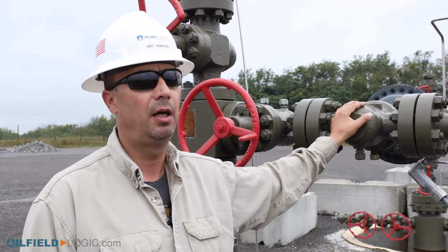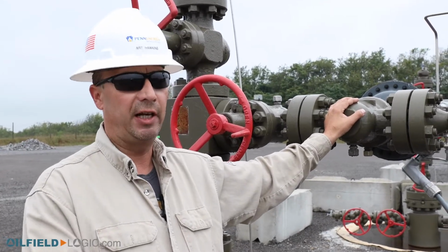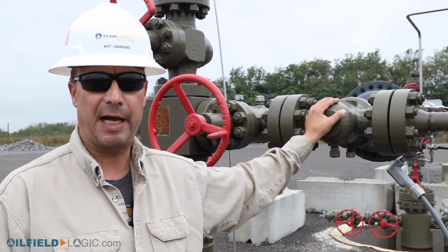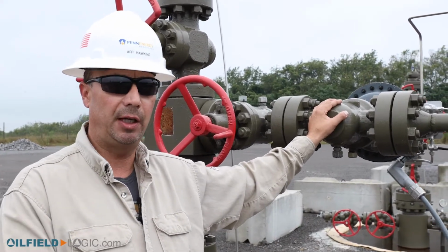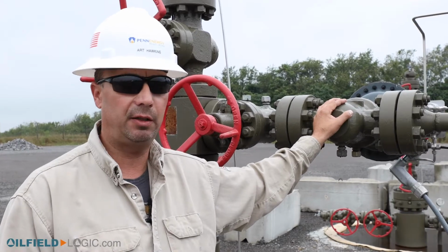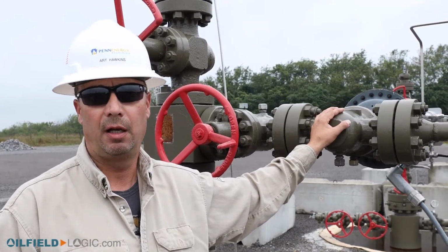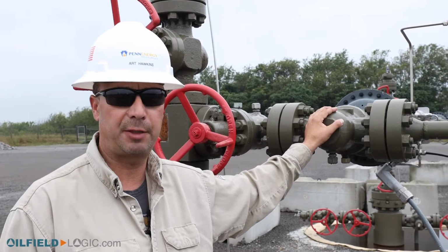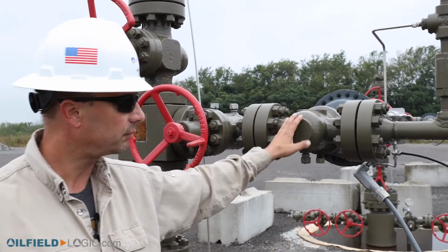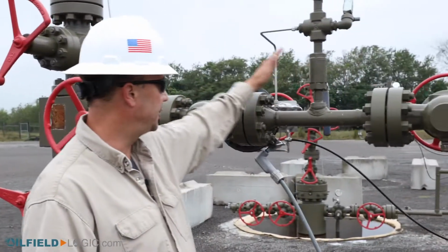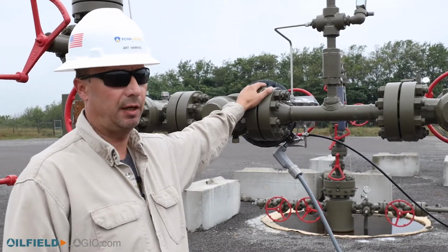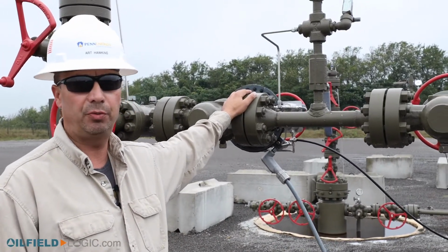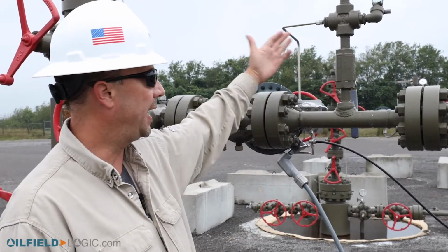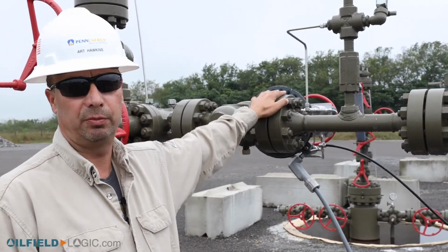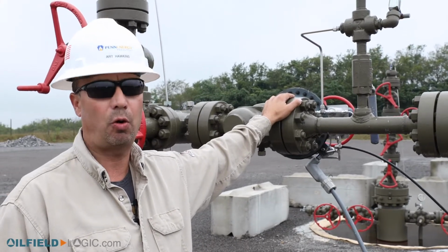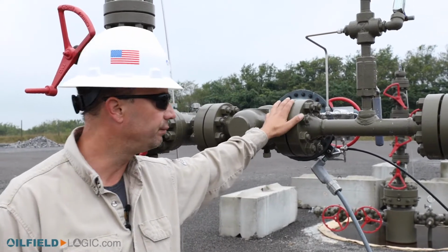This will shut in. If we are having an issue over on the GPU or gas production unit side, it'll shut in and separate the well to the inlet to the production to eliminate environmental spills and exposure to the atmosphere. We have sensing lines tied to the ESD. If for some reason our electrical devices do not shut in the well, we have mechanical devices as a backup that'll trip and shut the ESD on low pressure or high pressure purposes also.